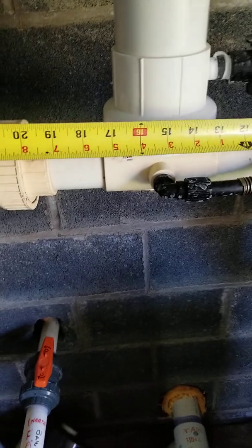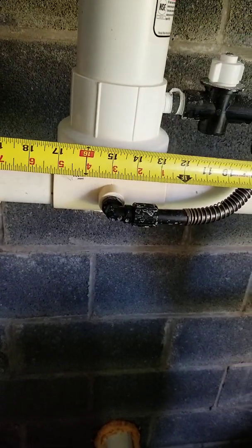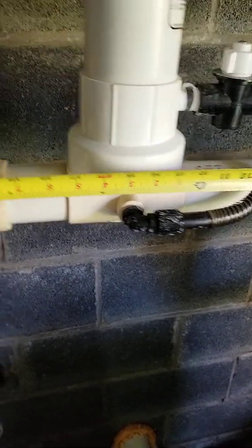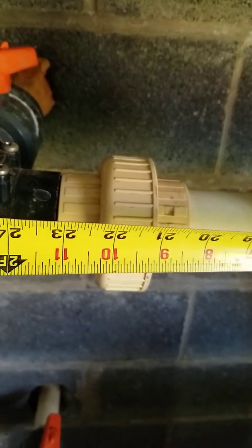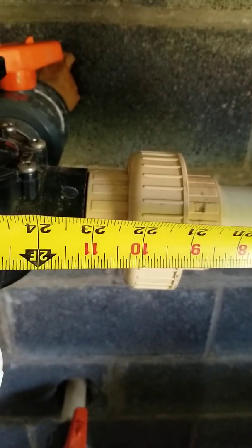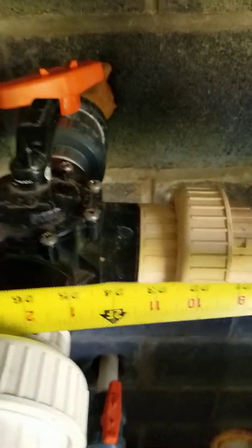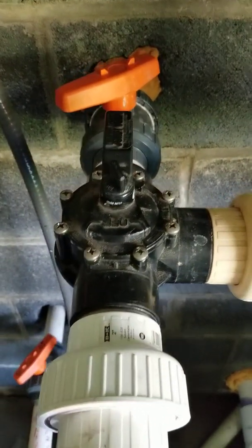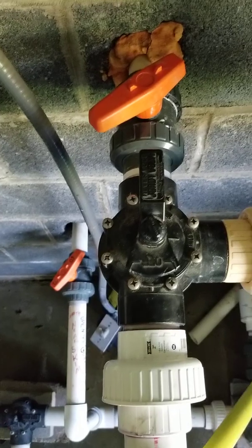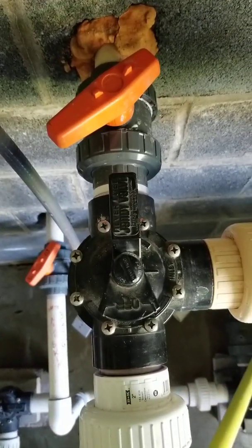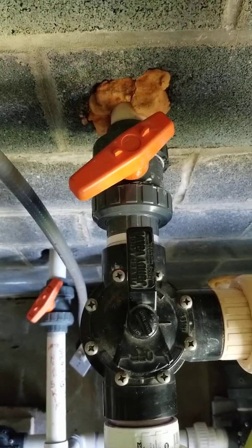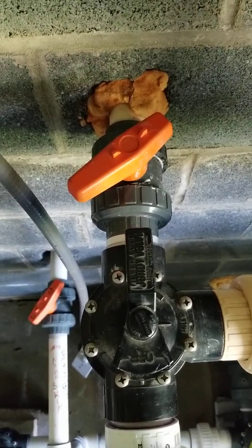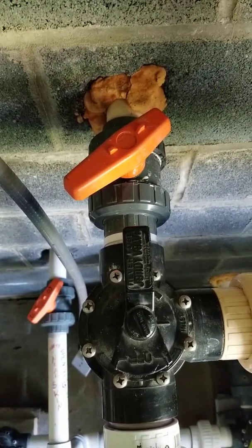I'm going to treat this as a length of straight pipe because I don't know anything better about it. I have 23 inches of straight pipe to my next 3-port valve. I'm going to treat that again as a T with branch flow. And then I'm through my other valve, and that valve right there is the one that leads to the fountain. And we're going to be calculating the pressure drop across that valve.